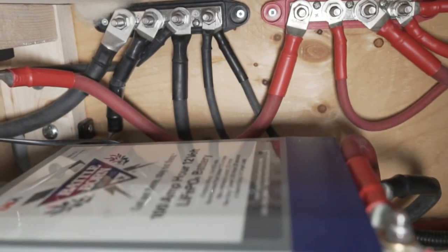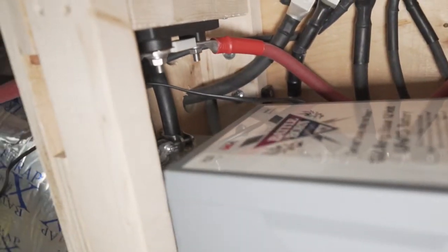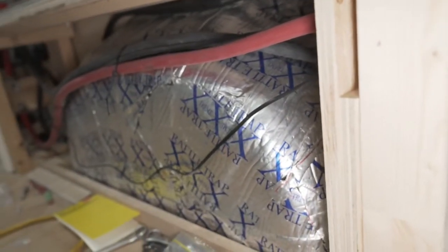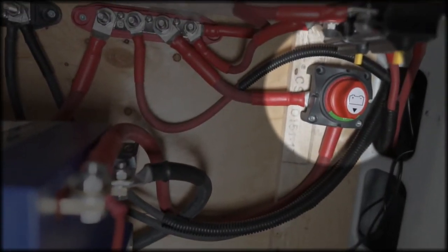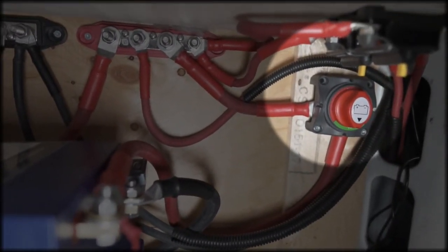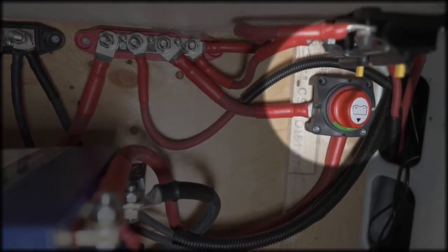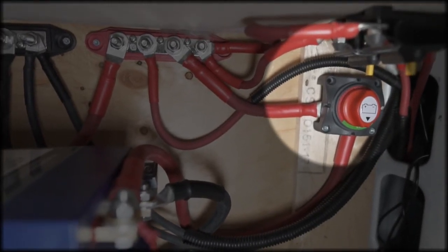So there's the plus and negative bus bars at the back. There's the fuse that connects the plus bus bar to the inverter charger. It's a 300 amp fuse, and then the cable runs up towards the front where the inverter charger is.